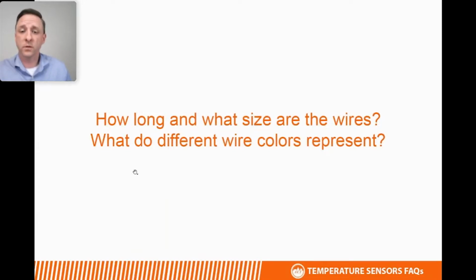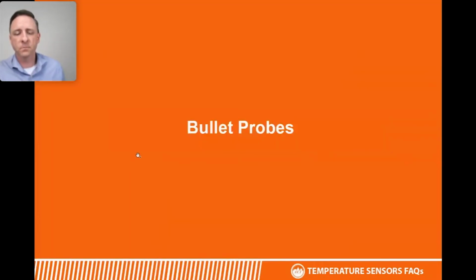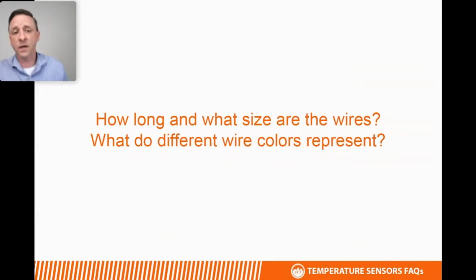How long are the wires, what size, and what do the different wire colors represent? For the wire lengths, I would refer you to the data sheets. There are standard wire lengths for all of the different configurations, and those are called out on the data sheets. For standard duct sensors, the wires are either 14 or 24 inches long, depending on the length of the probe, and that includes the probe length. For probes 8 inches and shorter, the wire is going to be 14 inches, including the probe. For 12 inches and longer, they're going to be 24 inches, again, including the probe. They are all 22 gauge wire.